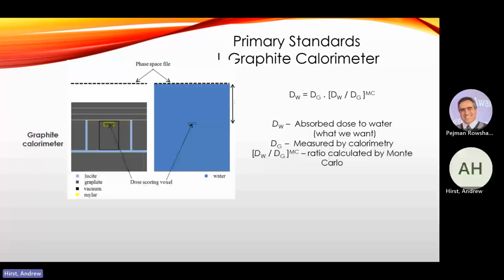So to convert to dose to water from dose to graphite, they use Monte Carlo modeling. They model the calorimeter on the computer and do a simulation between water and that calorimeter itself and get a ratio at the same location. And then by multiplying your measurement from the calorimeter itself by that ratio, you can get dose to water.